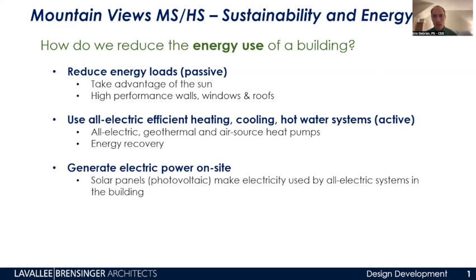The other technology we utilize that's extremely important is energy recovery. Unlike your house or a building you're familiar with, a middle school or high school has a lot of ventilation air being brought into it the entire time the school is occupied. That's fresh ventilation air to make sure indoor air quality is where it should be, student health is being maintained, and levels of alertness in the classroom are kept up. No matter what we do with the architectural envelope, a lot of ventilation air needs to be brought into the school, and consequently the stale air gets exhausted out.